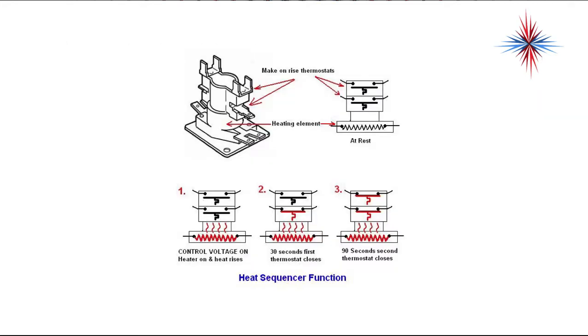Again, we take a look at the inside of this. We have a heating element, and when it's not energized, these contactors are open. There's a little bimetal piece of metal on here that's cool right now, at rest. We put control voltage into the bottom two terminals. The heater comes on and the temperature begins to rise.